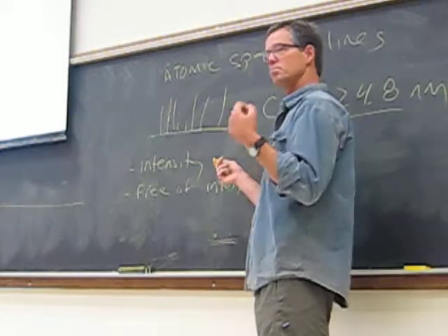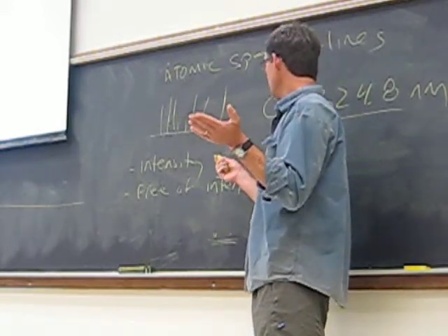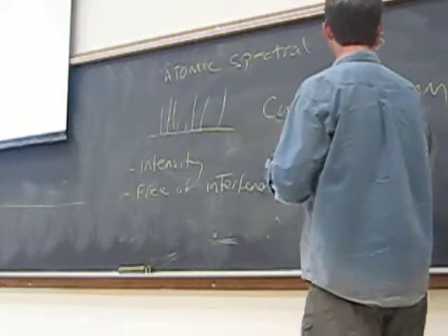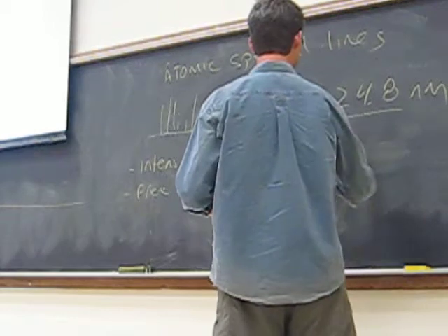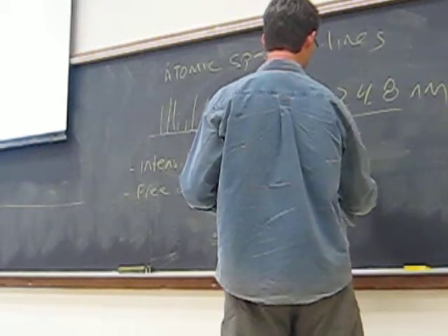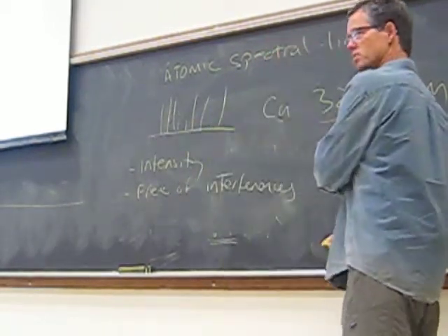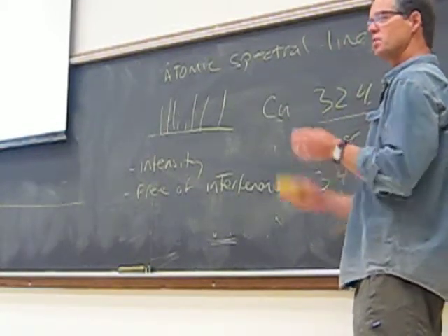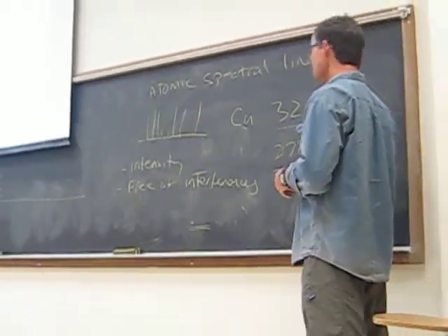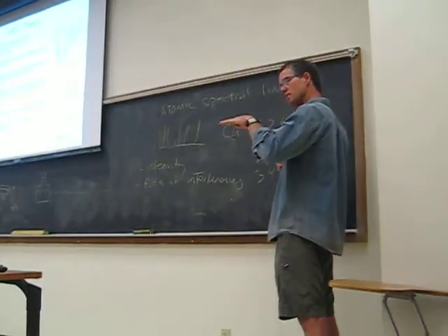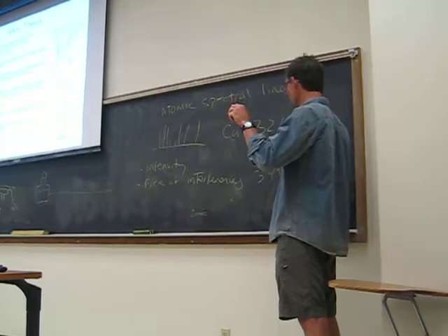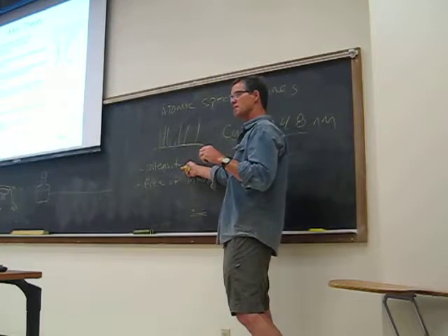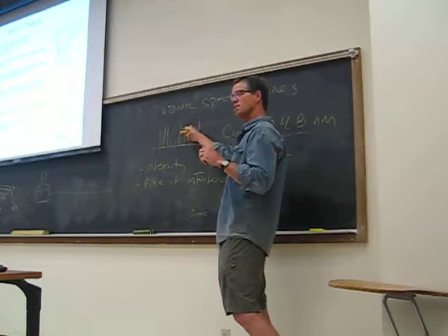How would you know, as a young analyst, let me back up, you could say, well, I've got a couple options. I know there's also a spectral line at 278 and another spectral line at 345. I'm making these up, and so I'm going to set the instrument to that, because I'm going to take the path least traveled. And you would likely measure a substantially lower energy level for the current of the lamp at these alternate wavelengths because not as many photons are striking the detector because they're less intense spectral lines.